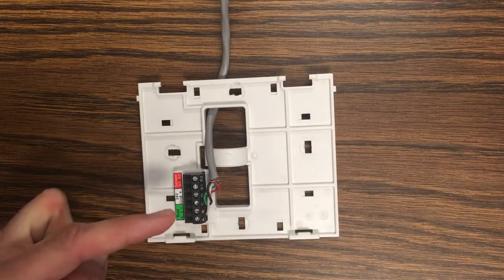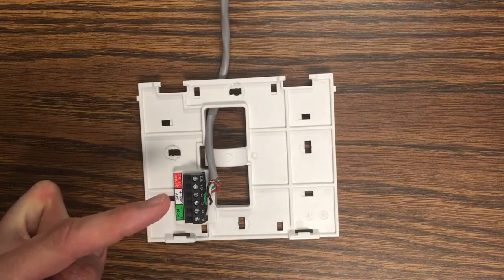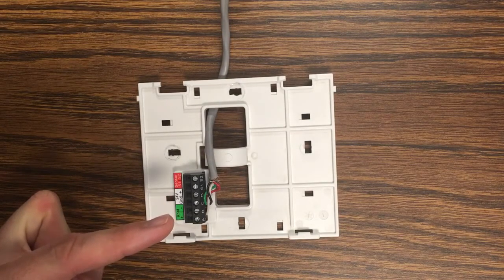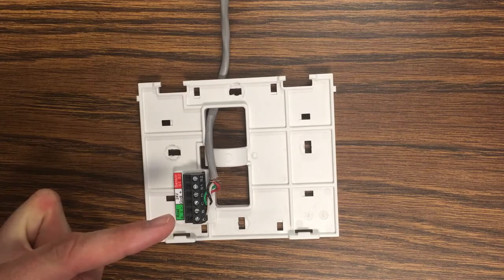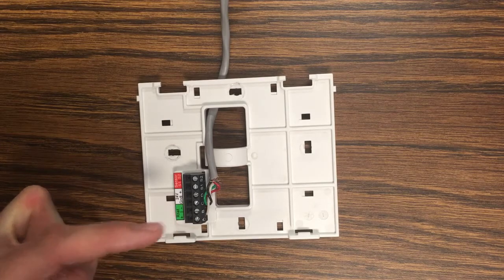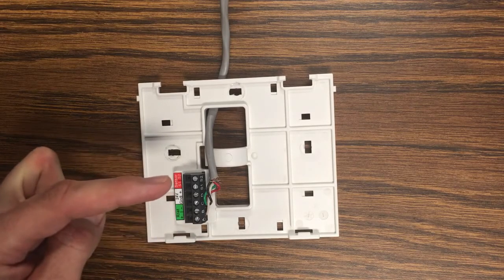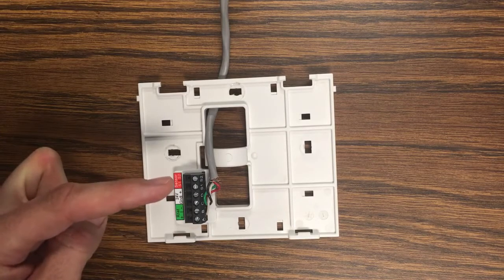If we take a look at the back plate the wiring is very simple. We have 24 volt hookup here. We've got our R-Net here which is the communications between the touchscreen and the controller plus to plus minus to minus on either end. And then we have a spot for an optional thermistor here.